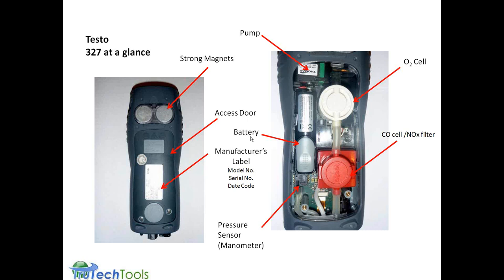The usage of the meter doesn't usually affect the quality of the sensors or how long they last, unless it's really hard use. It's usually more about just degradation. The oxygen sensor is pretty much like a battery. It has a liquid electrolyte in it that reacts with oxygen in the air. Once that liquid electrolyte is all consumed, the various constituents in it are consumed, then it's no longer going to be functional. So it's got kind of a combination of shelf and usage life, but it's in the 4 to 5 year time period for how long it would last.